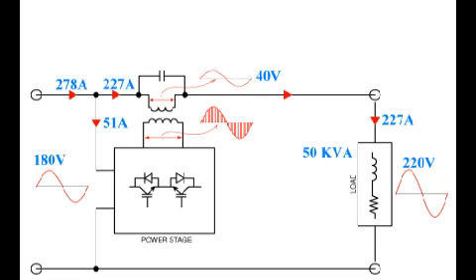Now you can see the operation of the stabilizer in boost mode. This is a 50 kVA stabilizer in boost mode — the input voltage is 180 V and the output is 220 V, so 40 V is added. That 40 V is generated by PWM and added to the mains. At 50 kVA the output current is 227 A, but at 180 V input it is 278 A, so the difference of 51 A flows through the IGBT.